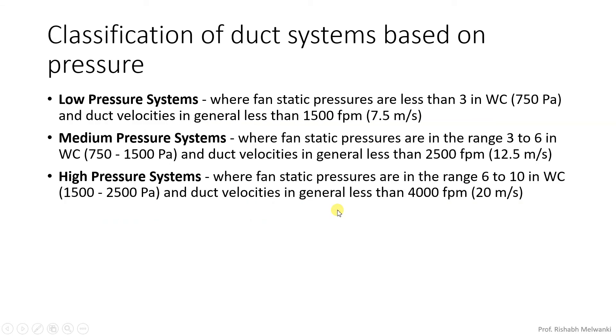Next is classification of duct system based on pressure. This classification has been made based on fan static pressure. When fan static pressure is less than 3 inches of water column and duct velocity is less than 1500 FPM — that is 7.5 meters per second — we consider it a low pressure system. In a medium pressure system, fan static pressure is in the range of 3 to 6 inches of water column and duct velocity in general is less than 2500 FPM — less than 13 meters per second. For a high pressure system, fan static pressure is in the range of 6 to 10 inches of water column and duct velocity less than 20 meters per second — these are high pressure systems.